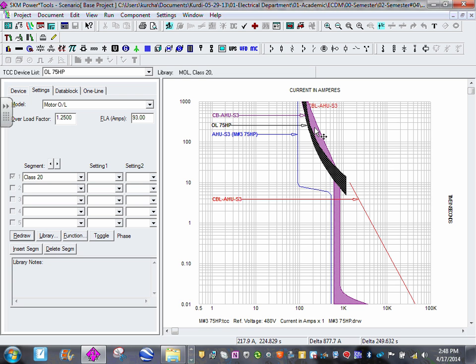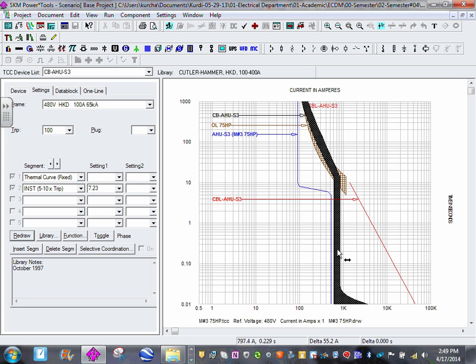I mean, SKM is a well-respected software. You can get from 250 down to 100 amp. You don't have to go that low, but I use this as an example. That's an example of how we can go much lower than what's in the code book, and by doing it this way you reduce the arc flash on that controller. If you have to work on it, the PPE category is lower, safer, right?